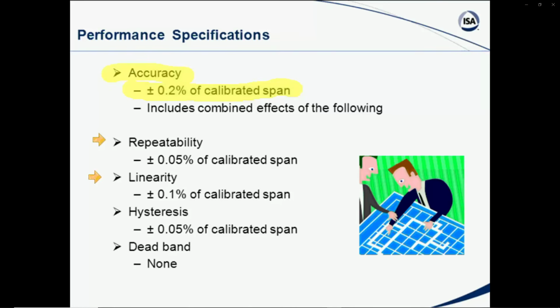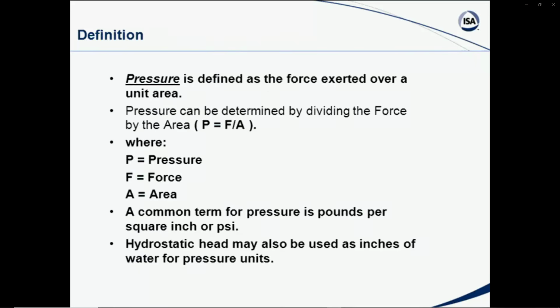The linearity we talked about, that's the ability to have an equal change in output to an equal change in input, and that can be caused nonlinear, give us some hysteresis on that, and occasionally there could be some deadband, where when you reverse directions on the input to the transmitter, nothing happens initially. Could have a little deadband, not very much in most of our newer or later electronic transmitters. So that has to do with the performance spec that you might see in different transmitters.